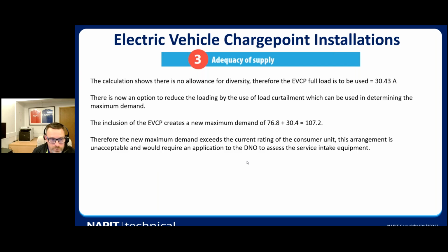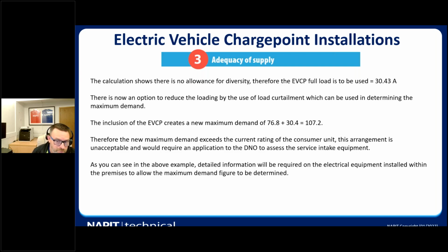But if you didn't use load management, the rating of the consumer unit would be unacceptable, and you would require the DNO to assess the service intake equipment to see if it needed an upgrade. So with the example, you can see what you've got to look at to see what the maximum demand is and what needs to be determined for assessing an electrical installation for an EV charge point. And in this instance, when it goes over the maximum demand for the installation, the form would be sent to the DNO.